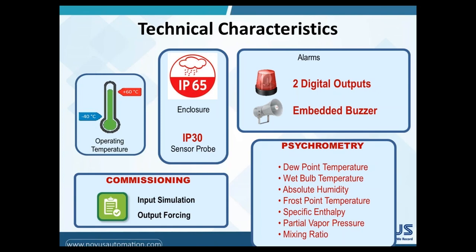The RHT Climate constantly calculates all seven psychrometric properties from the measured relative humidity and temperature. Those properties can be presented on the display, transmitted to the analog output, or read from the Modbus table. The seven properties are: dew point temperature, wet bulb temperature, absolute humidity, frost point temperature, specific enthalpy, partial vapor pressure, and mixing ratio.